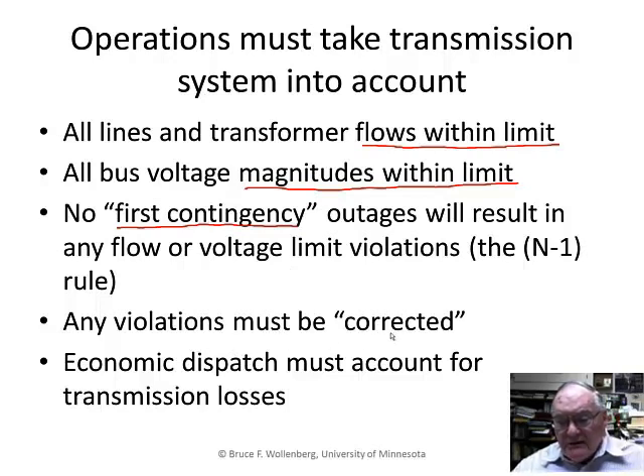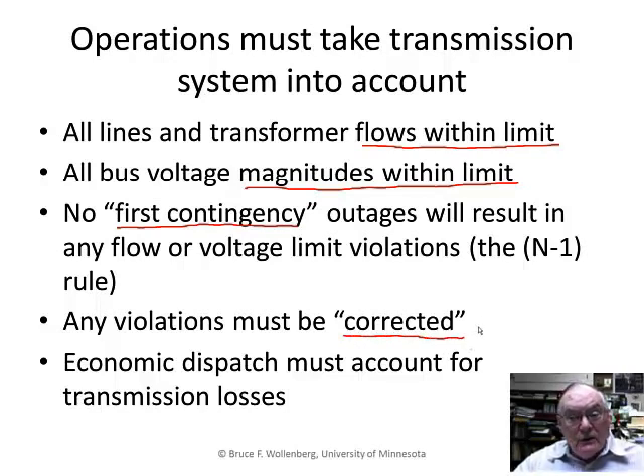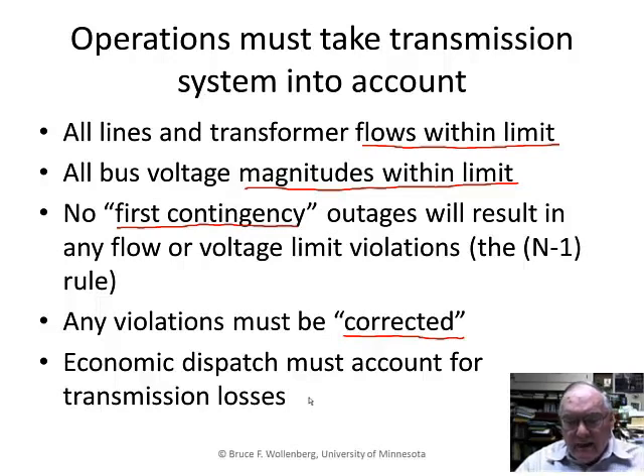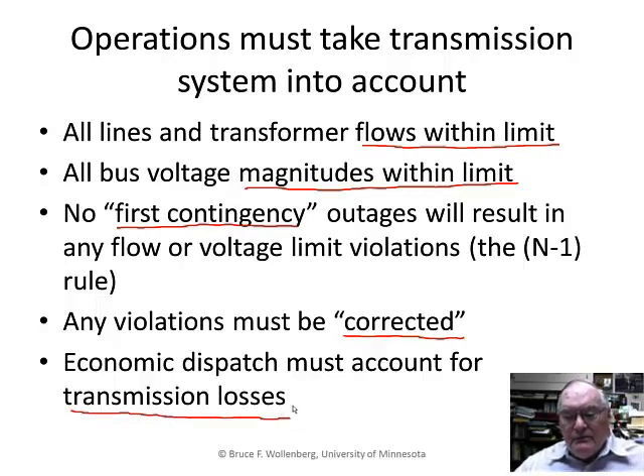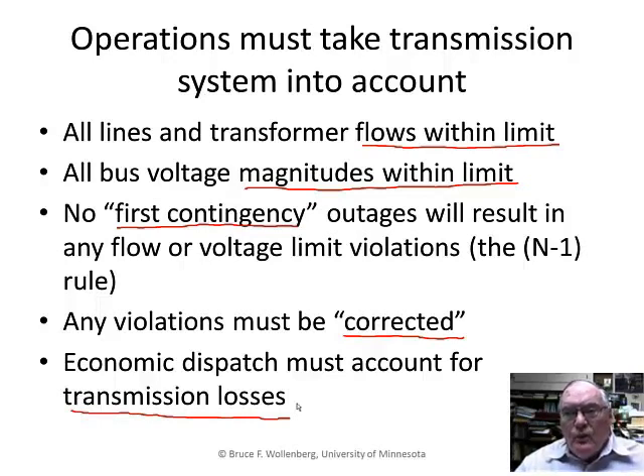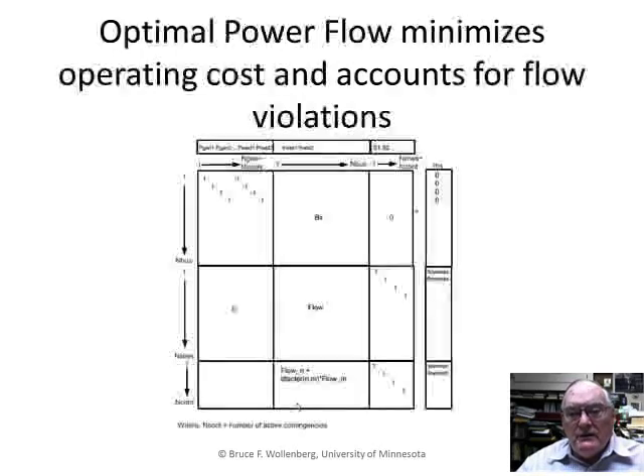Violations must be corrected, usually by changing the pattern of generation — going off of economic dispatch. They must be corrected in real time, as fast as possible. And lastly, economic dispatch must account for transmission losses: the I-squared-R losses that cause lines to heat up. There's a small but significant amount of loss, and while we can't eliminate all losses, we can minimize their economic effect.